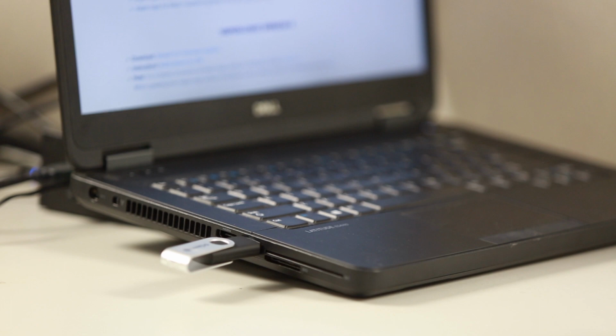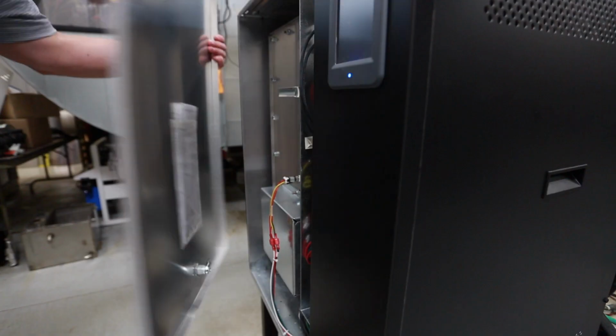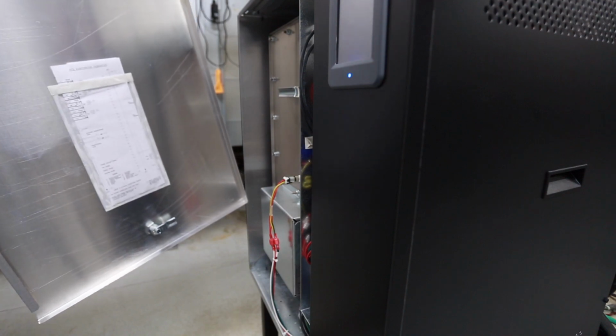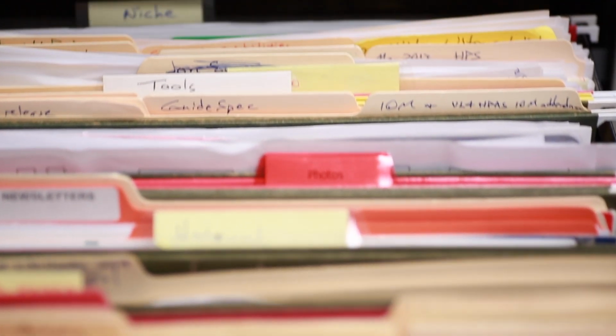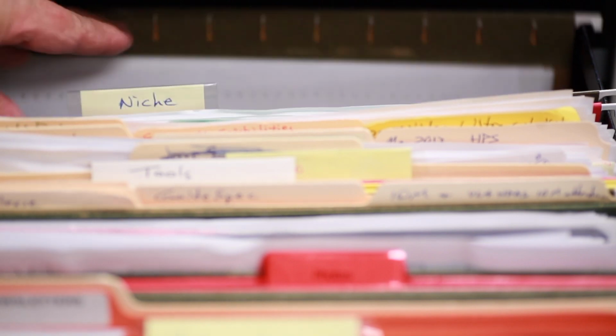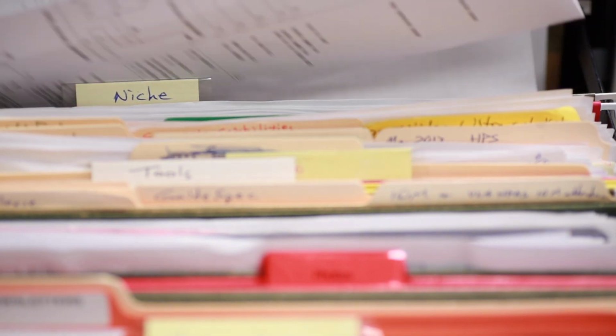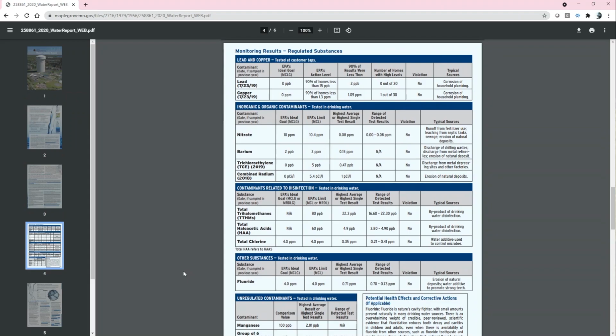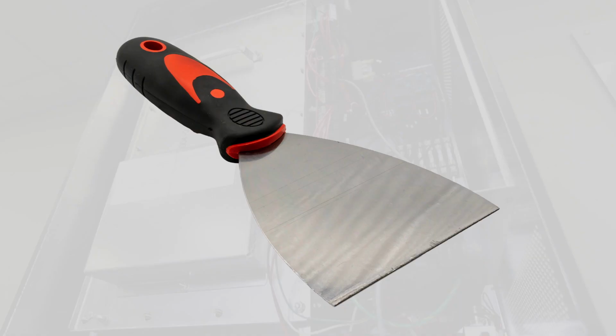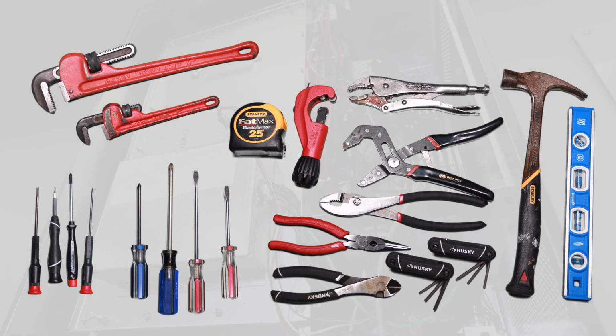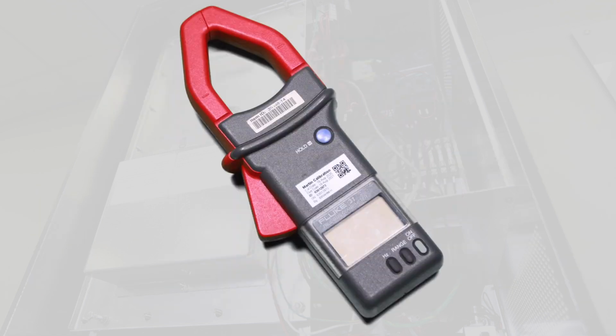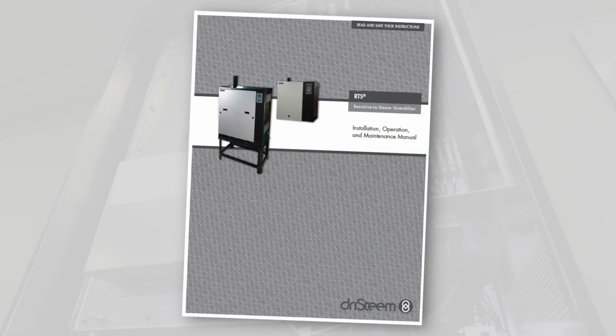A USB flash drive with the most current version of the controller firmware, wiring diagram. The wiring diagram is supplied with the humidifier, but it's a good idea to bring one, as the supplied one might not be easy to find on site. Your DriSteem rep can email you the wiring diagram. Building water test report. Most municipalities have water reports online. Cleaning tools, example putty knife or scraper. Basic hand tools, drill with driver bits, clamp, meter, and of course the RTS IOM for detailed information on how to perform the maintenance tasks.